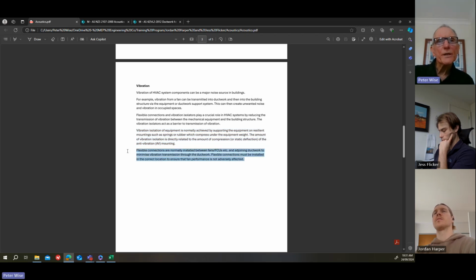And you'd also be aware that flexible connections are normally installed between fans or fan coil units and the adjoining ductwork. This is just a short section of what we used to call canvas. They don't really use canvas anymore. They use a polyester material, but it's only about 100 to 150 millimeters long to give vibration isolation between the fan and the ductwork. So you've got the springs or the rubber allowing the fan to move. As it rotates, it's going to vibrate a bit. But because it's moving a little bit, the vibration is set up that will enter the ductwork unless you have a flexible connection there. So if that's all done correctly, that will eliminate the vibration into the ductwork.